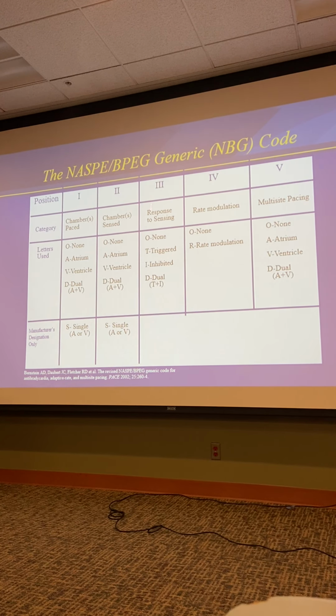Okay. If you want to make the device more sensitive, you set the sensitivity to a lower number. So for R waves that might be 7 millivolts or R waves that might be 3 millivolts, if you set the threshold at 4, the pacemaker will see this R wave and it will not see this R wave. If you set it at 2, it'll see both. The lower you set it though, the more it becomes vulnerable to things like the electrical signals from the chest wall muscles or other sources of noise. So you want to set the threshold high enough to not let the device be tricked by seeing noise, but low enough that it will reliably see every R wave or every P wave that comes by. And that's why when we implant the leads, we always want the R waves and the P waves to be large enough that we can set a reasonable sensitivity so that the device can be reliable and not vulnerable to noise.